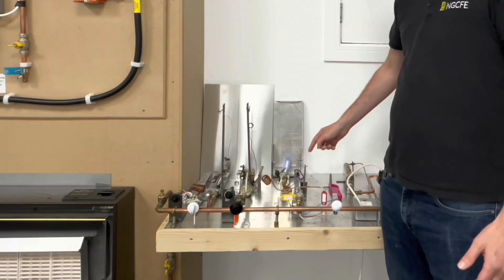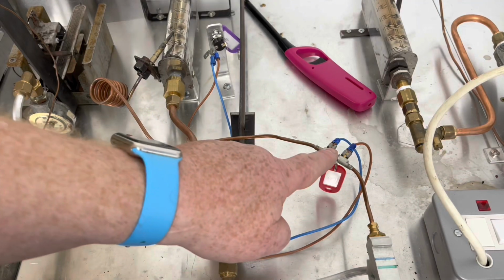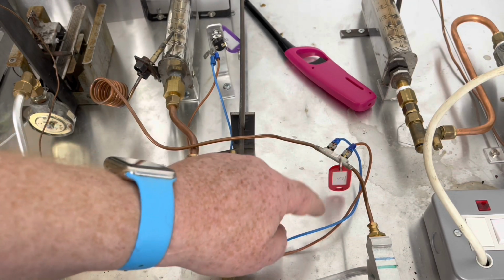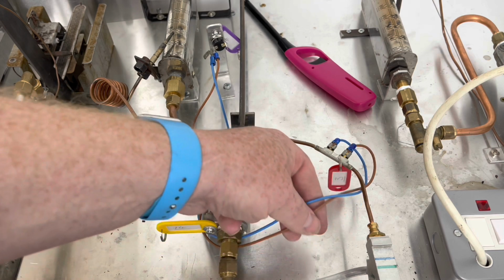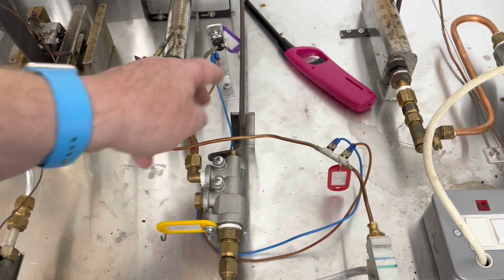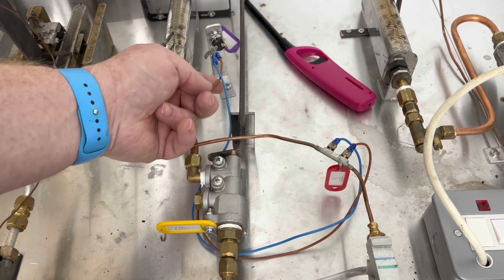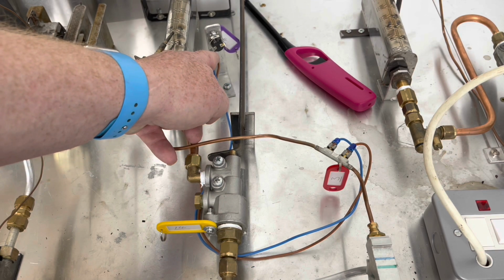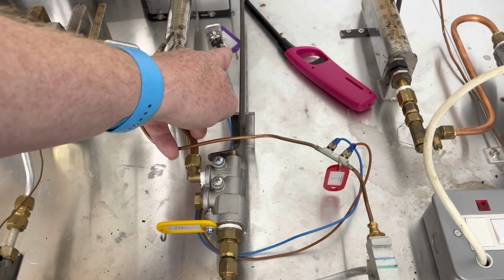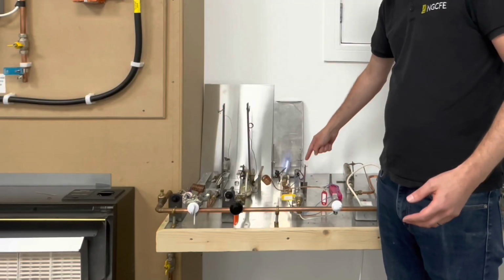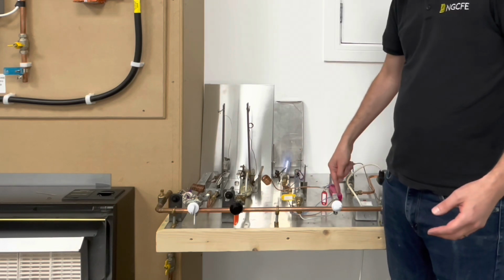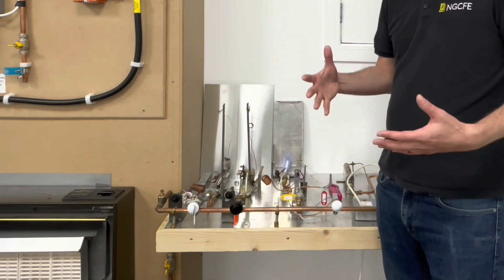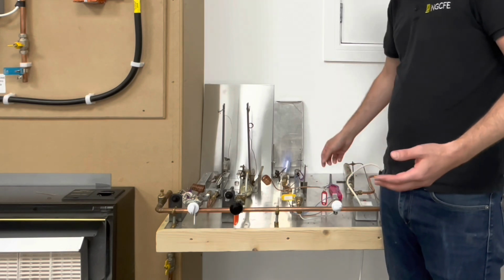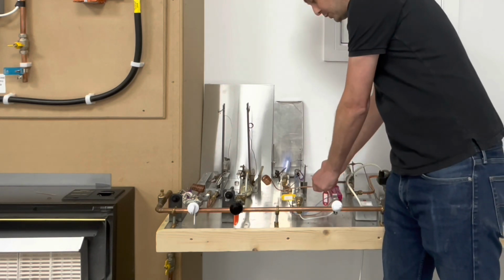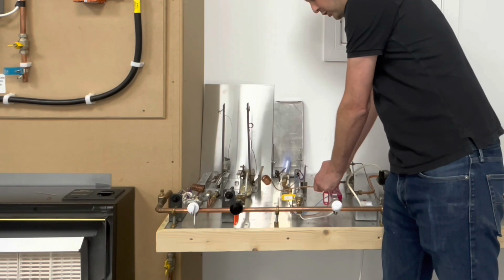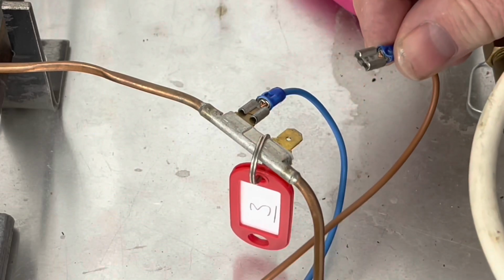What we've also got is the current and the voltage that is holding this valve open, but you can see we've got an interrupter wired in. That interrupter basically is wired to an overheat stat. So the current and the voltage is travelling through the tube, goes back through the overheat stat, and then back to the magnet, which is holding it open. If for whatever reason the overheat stat was to break, or it was to break its contact, the flame would go out.